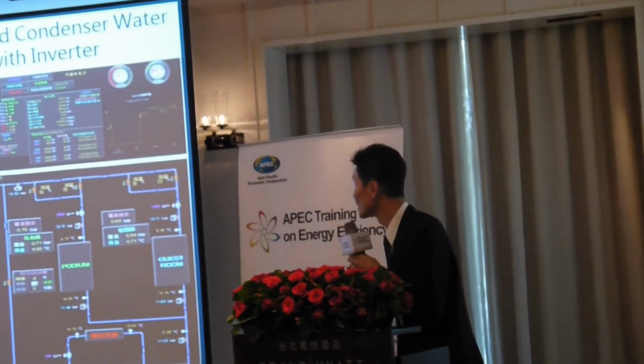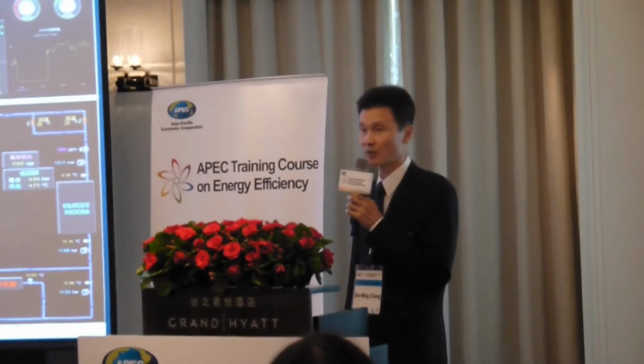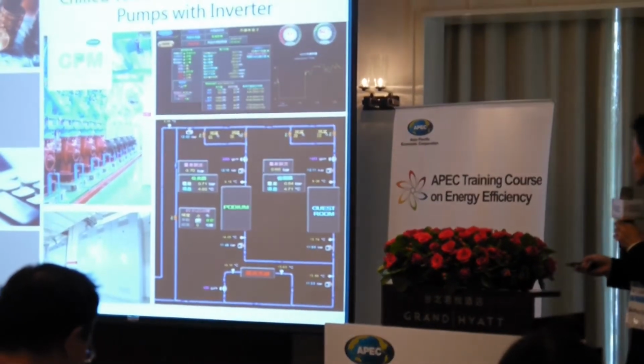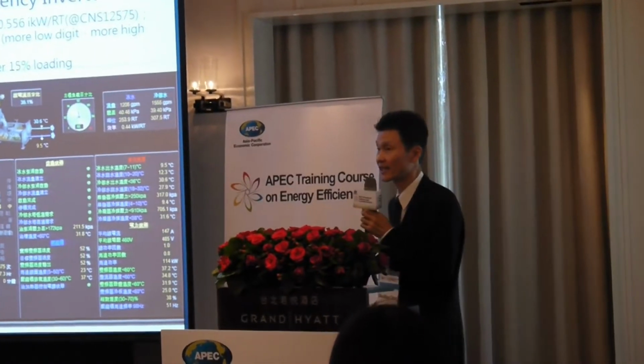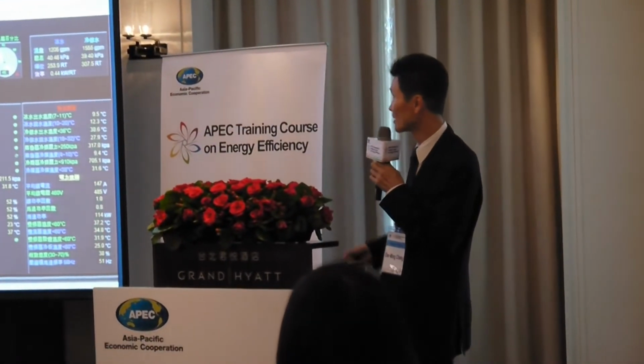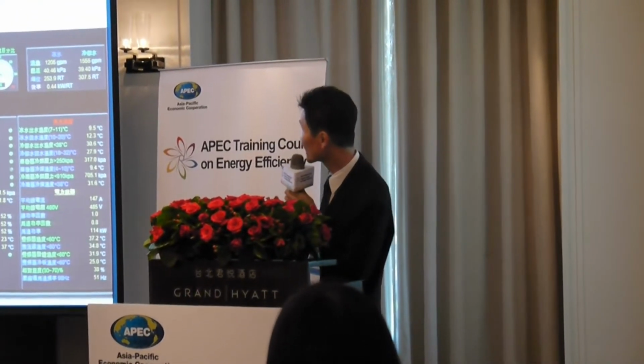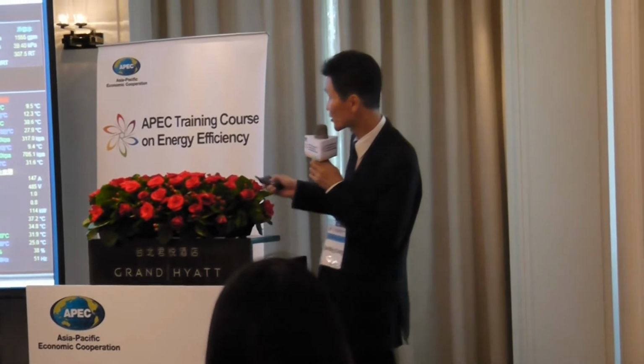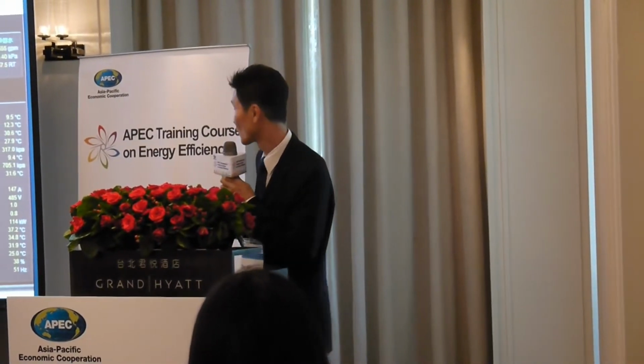Our chilled water and condenser water pumps are also with inverters. That means all the pumps have inverters. We know an inverter can reduce the speed in partial load, and reducing speed also gets us energy saving. So all the pumps are inverter controlled. It can get higher efficiency of the chiller. This chiller can run down to near 15% loading. Usually a chiller at maybe 30 or 40% already surges and cannot run, but this chiller can run at 15%, very low.